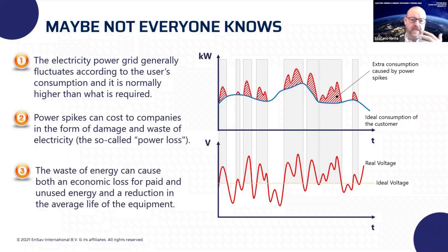These fluctuations, and in particular the peaks of this variation, can lead to several problems, and these are the problems we are trying to address with proper voltage optimization management. First of all, we can have extra consumption of energy, and therefore waste of money, on loads that are voltage dependent or voltage sensitive to different degrees — for example, motors, pumps, chillers, resistances, transformers, and lamps. Of course, as you may know, all these loads can have different degrees of sensitivity in relation to voltage.